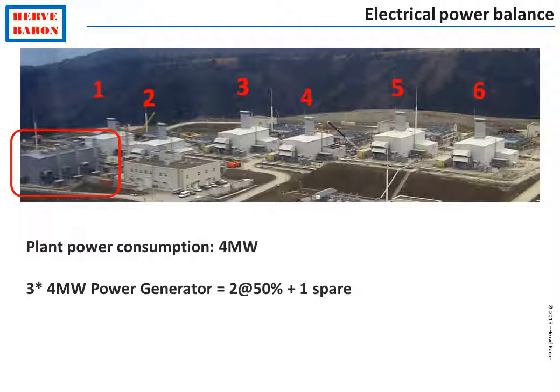This allows sizing of the plant power generators. As uninterrupted power is required, there are several generators to provide backup — if one fails, the others can compensate and take up the load. For instance, if the total power consumption is 4 MW, three generators each of 4 MW capacity would be a suitable selection. Two generators operate at 50% capacity and one is spare. If one generator fails, the other already running generator can go to 100% and take all the load.